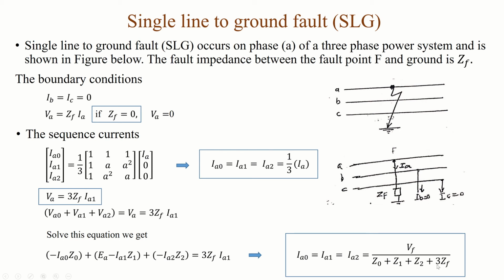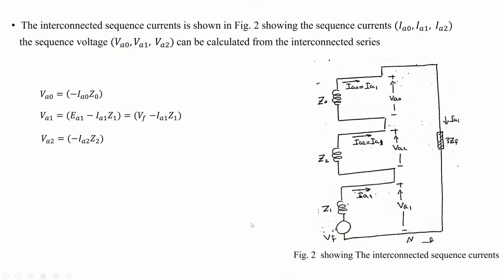If ZF has no value, that means this part is going to be zero. Also, all this equals 1/3 IA. So this is the fault at phase A. If you want to calculate the current at phase A, you have to calculate this sequence and then multiply by 3 to calculate IA. Okay? So the interconnected sequence current is shown in the figure.